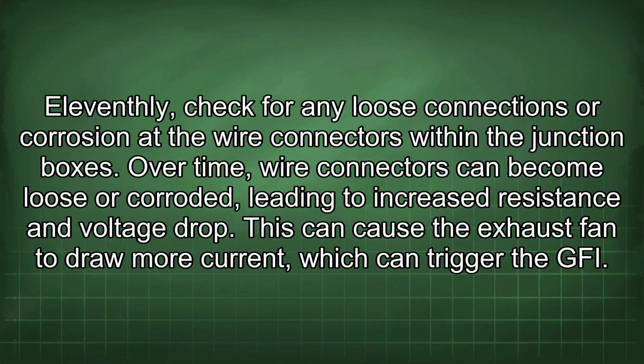Eleventhly, check for any loose connections or corrosion at the wire connectors within the junction boxes. Over time, wire connectors can become loose or corroded, leading to increased resistance and voltage drop. This can cause the exhaust fan to draw more current, which can trigger the GFI.